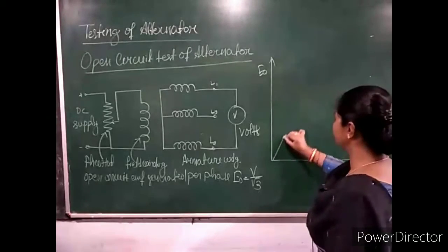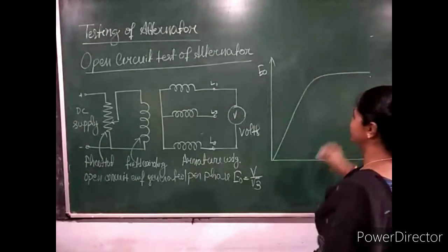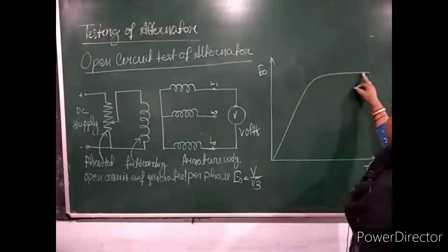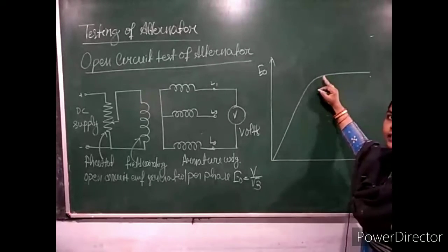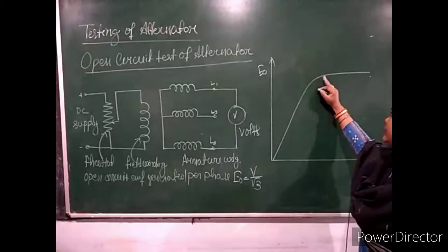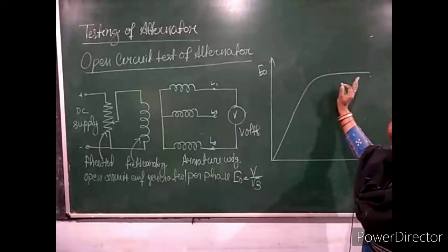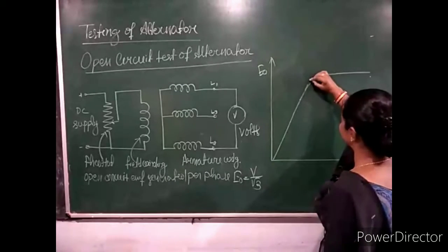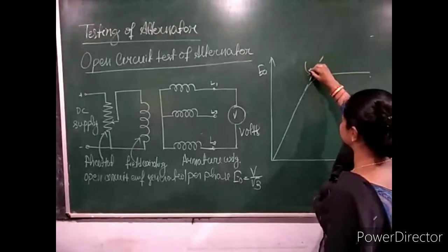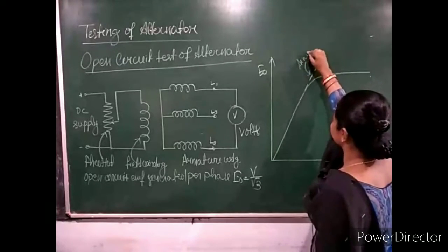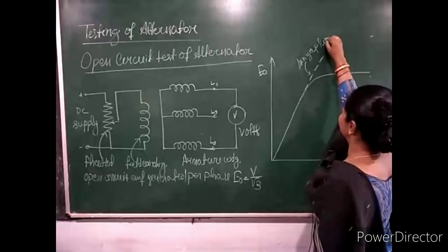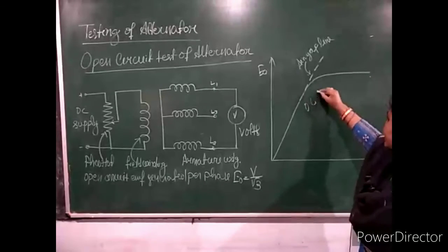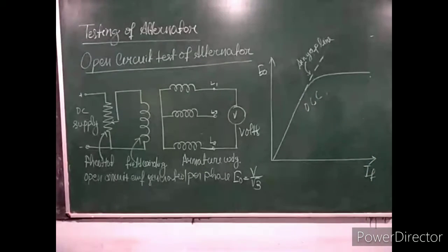The nature of the curve is like a magnetization curve. It increases up to some value, and after reaching its rated value, it comes to saturation. If I extend the straight line portion, it is called the air gap line or air gap characteristics. This curve shows the open circuit characteristics of an alternator.